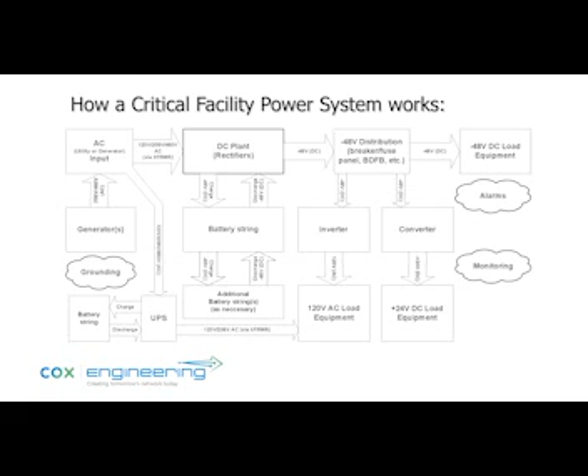So first of all, the AC power comes in, it's rectified, converted to DC power by the DC plant, which is a bunch of rectifiers. Now, that DC power is used to power the load and then trickle charge the batteries. When the AC fails, the load is powered by the batteries alone. Over time, the battery voltage drops, and we typically engineer a 4-hour backup for sites with dual generators, 8-hour for a single generator. Now I should have changed that to 3 hours and 5 hours.